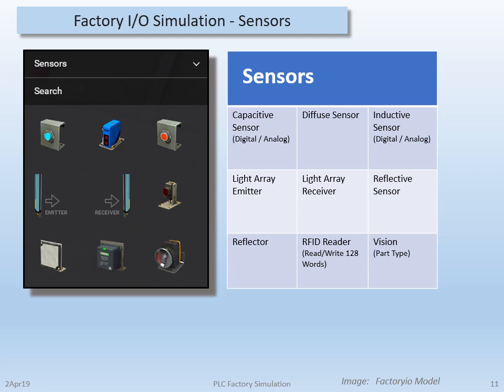The capacitive and inductive sensors have an additional feature of being able to output a value via an input word to the PLC to indicate how close an object is to the sensor. Also shown here is a light array made up of a sensor receiver pair with multiple outputs that can be used for object height detection. A retroreflective and diffuse optical sensor is also included. A recent addition of an RFID reader and vision sensor is pretty exciting, and I'll get into this more in a few slides.